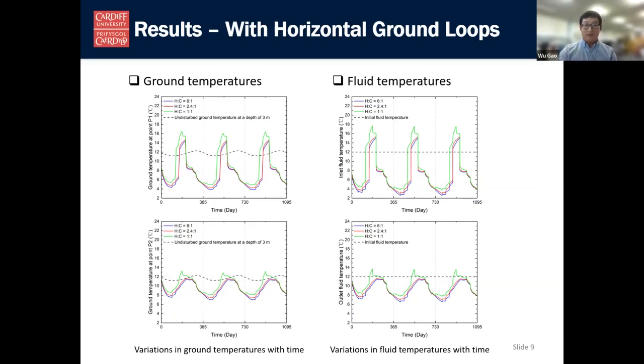As shown in the left figures, after installation of ground loops, the ground temperature declines significantly during the heating period compared to the undisturbed ground temperature. And once the cooling mode was on, the ground temperature increased or even became higher than the undisturbed ground temperature. After about 2 years, an annual periodic pattern in the ground temperature can also be observed. The inlet and outlet fluid temperature on the right basically shows a similar changing pattern.